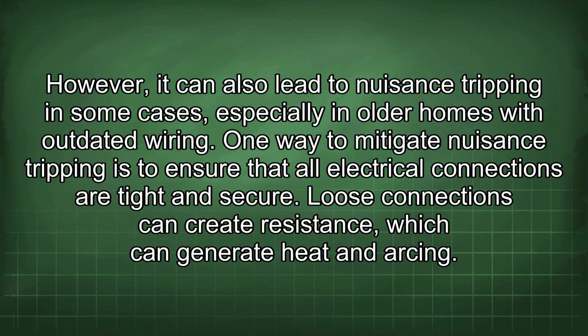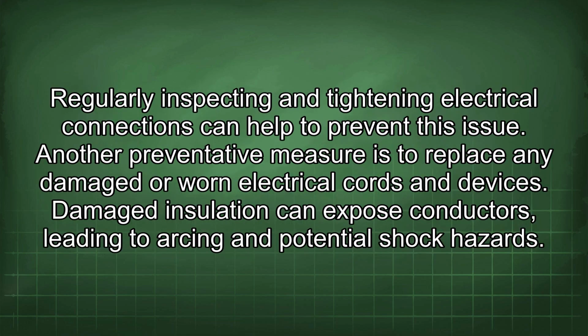However, it can also lead to nuisance tripping in some cases, especially in older homes with outdated wiring. One way to mitigate nuisance tripping is to ensure that all electrical connections are tight and secure. Loose connections can create resistance, which can generate heat and arcing. Regularly inspecting and tightening electrical connections can help to prevent this issue.